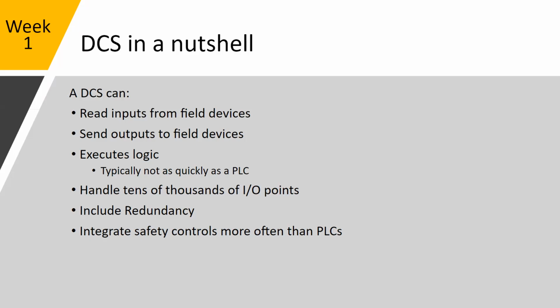Imagine if you've seen any of those solar farms with 150 acres of panels, all of those get wired back to IO boards inside inverter houses. Those inverters will have hundreds and hundreds of data points monitoring all of the strings, all of the voltages, the amperages. All of that would get relayed up to a main controller, whether it's called a DCS or a PLC. Some companies will call them RTACs, real-time automation controllers.